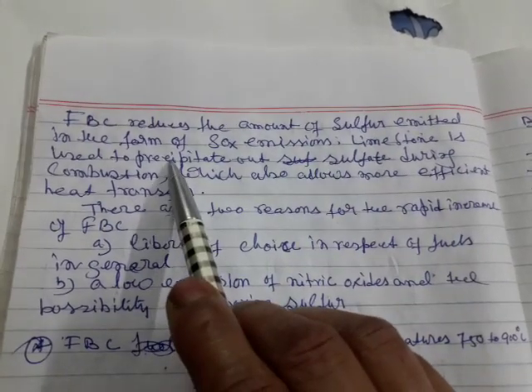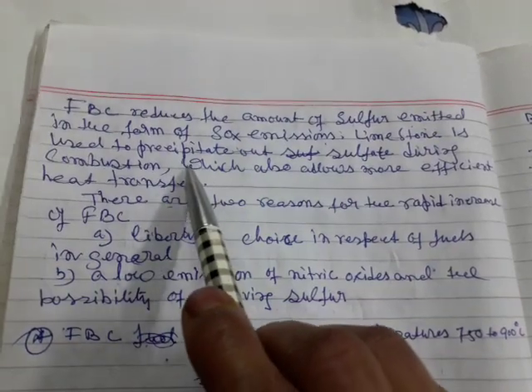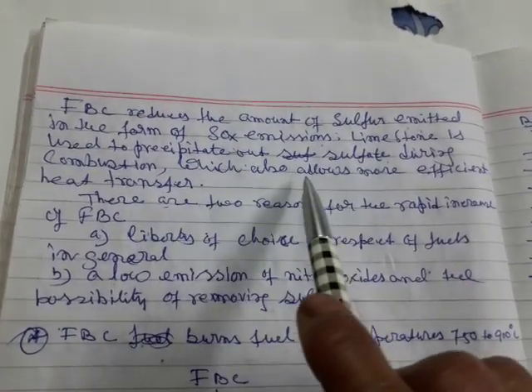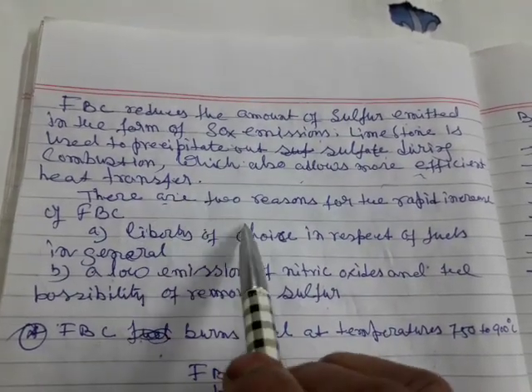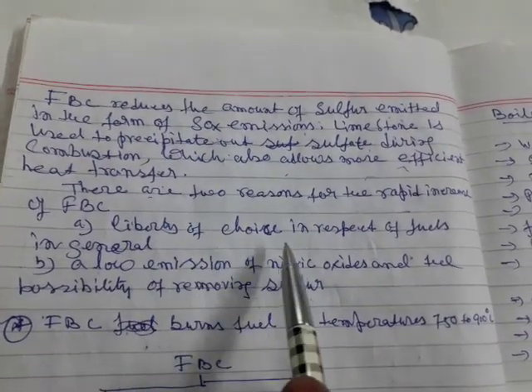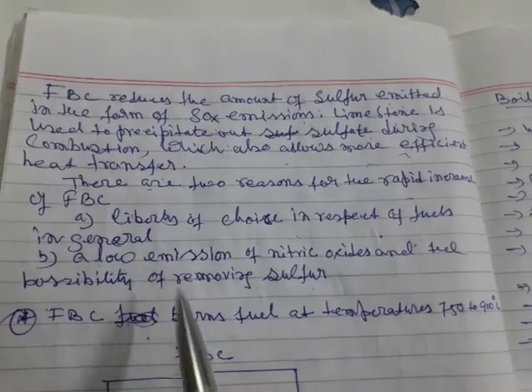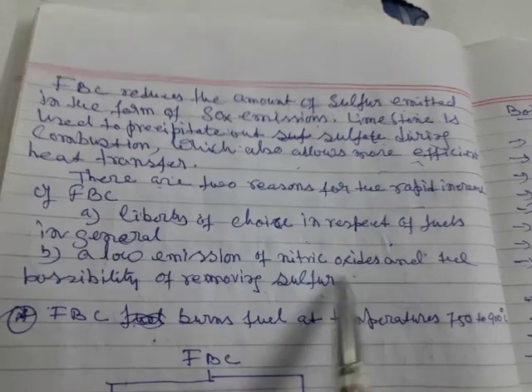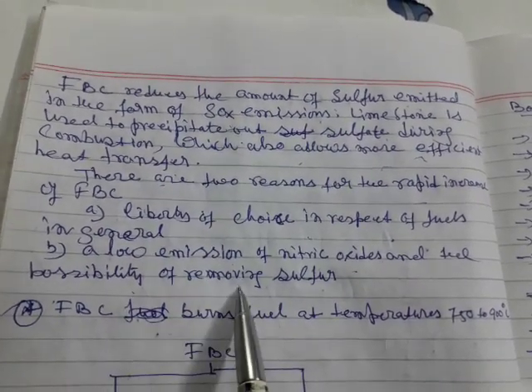FBC reduces the amount of sulfur emitted in the form of SOx emissions. Limestone is used to precipitate out sulfate during combustion, which also allows more efficient heat transfer. There are two reasons for the rapid increase of FBC: first, liberty of choice in respect of fuel; second, low emission of nitric oxide and the possibility of removing sulfur.